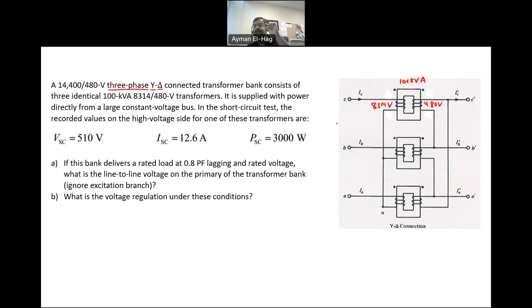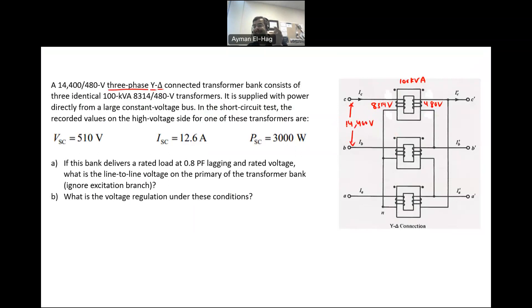Because the primary is connected as a Y-connection, the line-to-line voltage is 14,400 volts, which is root 3 times the phase voltage. On the other hand, the secondary is connected as delta, so the line-to-line voltage stays the same at 480 volts. This is how the transformer is connected as three-phase.